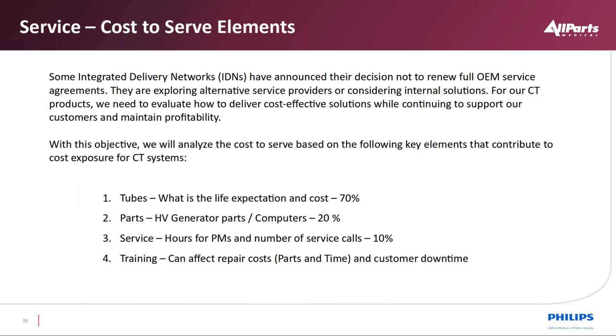So when we deal with cost to serve, there's a big push by a lot of groups to go in-house with regards to their programs instead of doing full service with OEMs. And then there are obviously independent service providers as well, what we call ISOs. So AllParts has the ability to support those. With regards to doing that, we have a number of CTs here that we use for evaluation of parts, but also we use and teach on them as well. So parts that normally might be just bench tested with other vendors, we actually put on our machines and scan with them here to validate image quality as well. So that might be a differentiator as well.